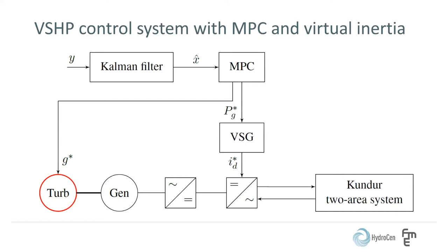This figure shows the layout of the proposed variable speed hydropower control system with model predictive controller, MPC, and virtual inertia. First, a Kalman filter estimates the states of the system. The MPC inputs this and optimizes the system by controlling the guide vane opening reference to the turbine and the power reference to the virtual inertia controller. In this case, a virtual synchronous generator called a VSG. The VSG outputs the current reference in the D-axis to the grid connected converter.